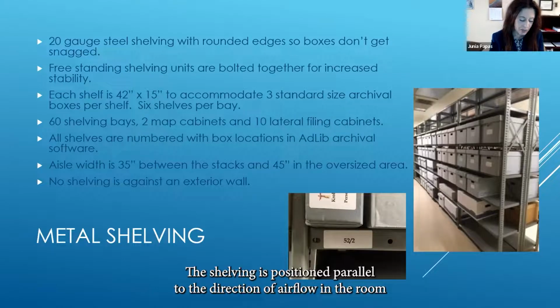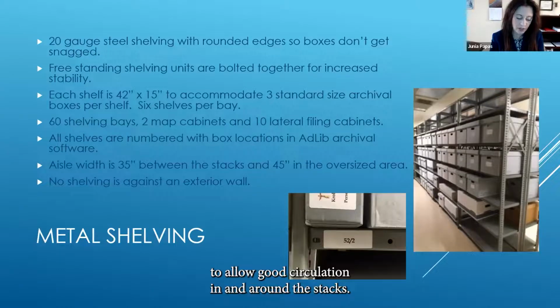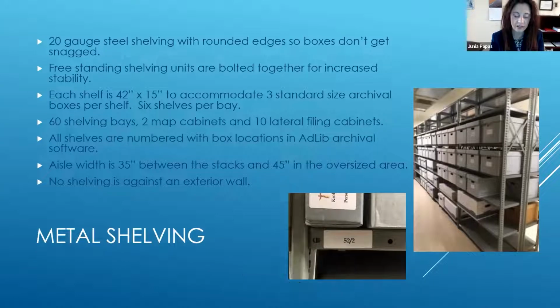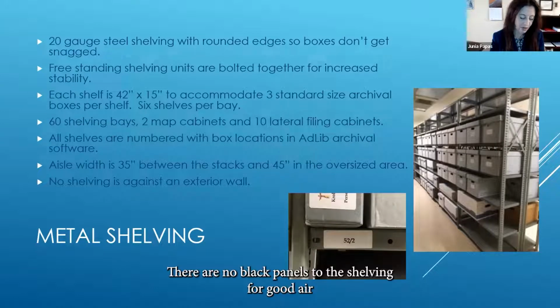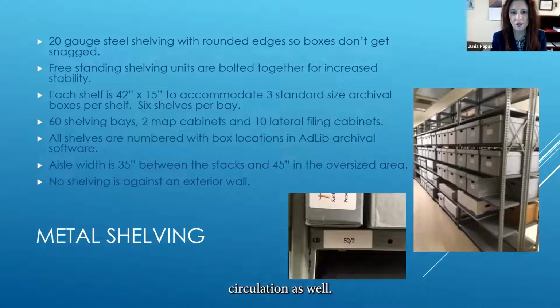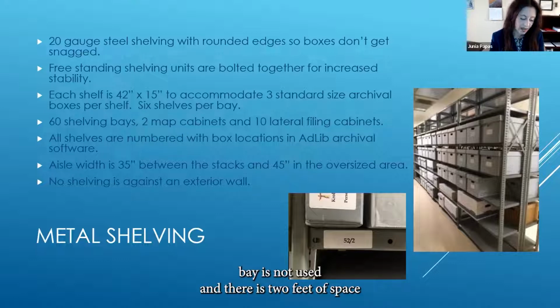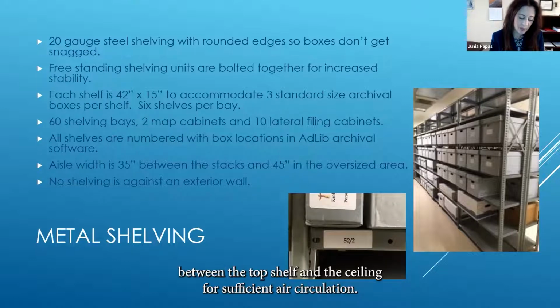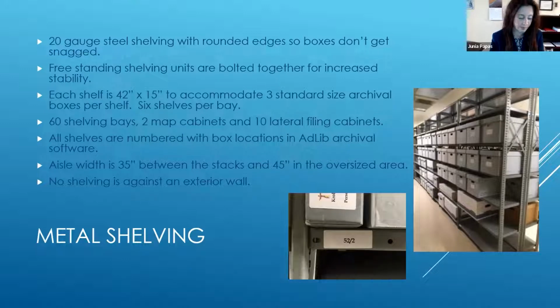The shelving is positioned parallel to the direction of airflow in the room to allow good circulation in and around the stacks. There are no back panels to the shelving for good air circulation as well. The very top shelf of each bay is not used, and there is 2 feet of space between the top shelf and the ceiling for sufficient air circulation.